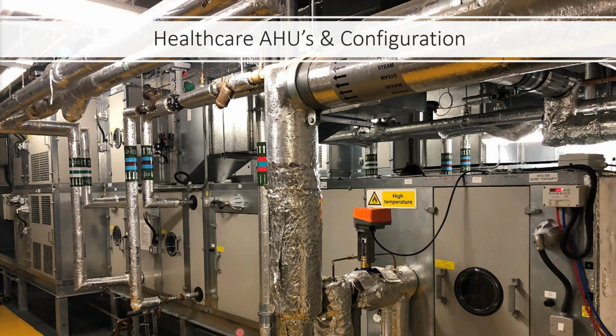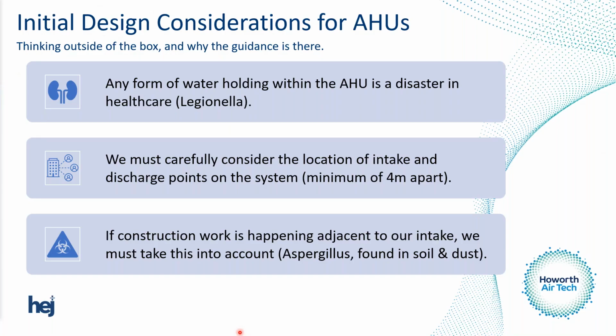So, healthcare AHUs and the configuration of those AHUs. Air handling units within healthcare are very specific. It's not a standard building services type arrangement, and these are the reasons why. We have considerations that we've got to make. There are lots of considerations, but I'll put some high level ones on this slide before I go into the nuts and bolts of it. So obviously within an air handling unit, any type of pooling water, and I'm going to talk about water control in the air handling unit in a moment, is an absolute disaster, because that can be a breeding ground for Legionella.